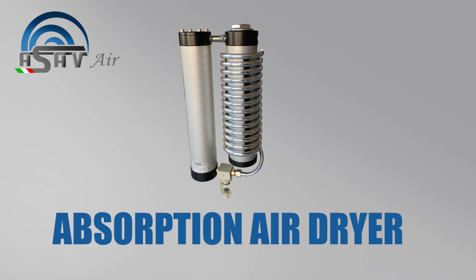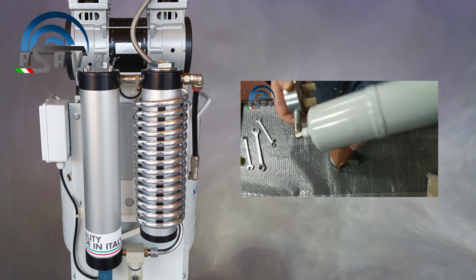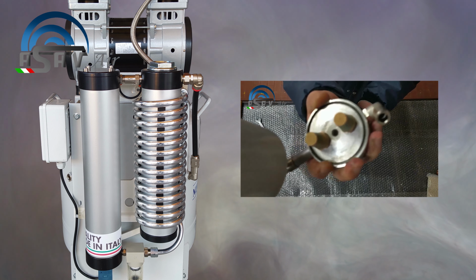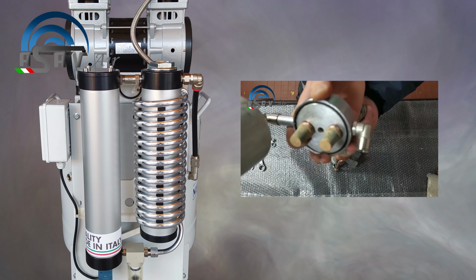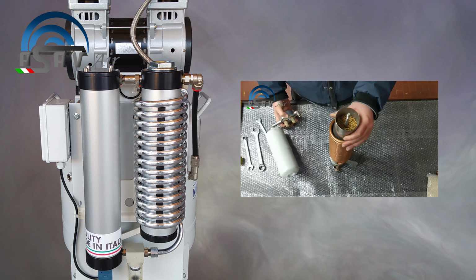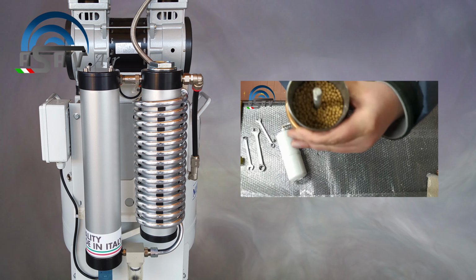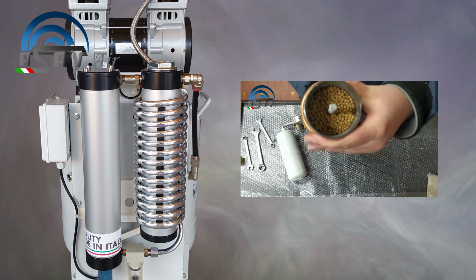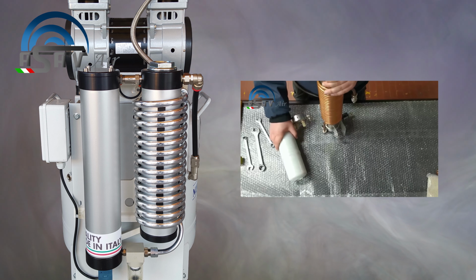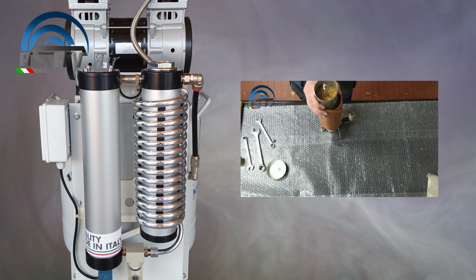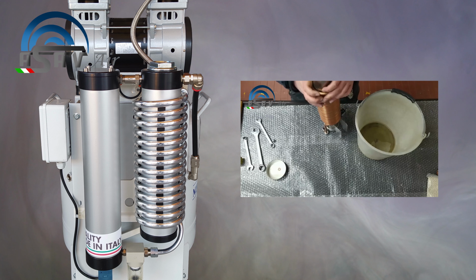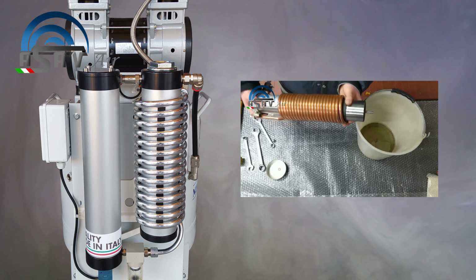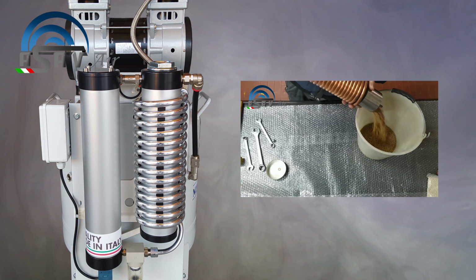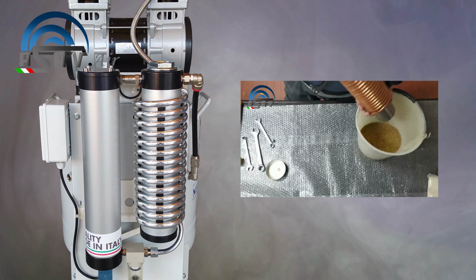This type of air dryer uses 1 or 2 towers, better 2, that contain a drying material, usually alumina or silica or activated carbon. One contains the desiccant that removes moisture from the airflow from the compressor. The other one regenerates the desiccant already used after the pressure has fallen under atmospheric conditions. The flow reversal cycle is automatic and the regeneration is performed first on one column and then on the other.